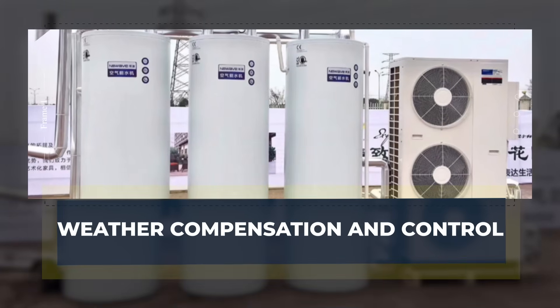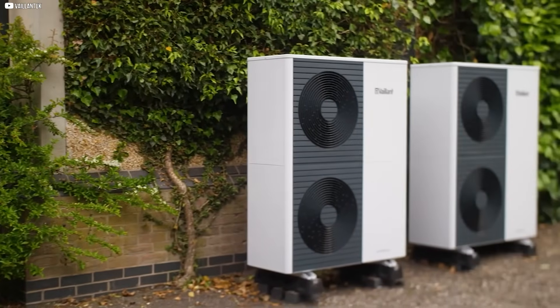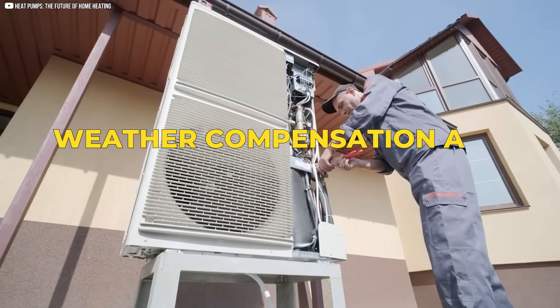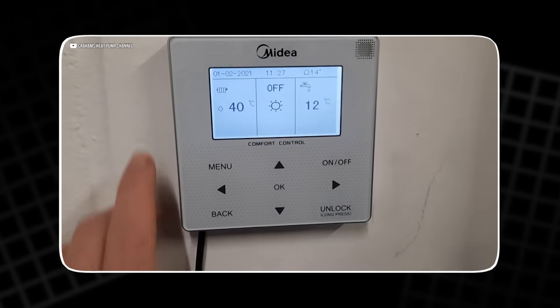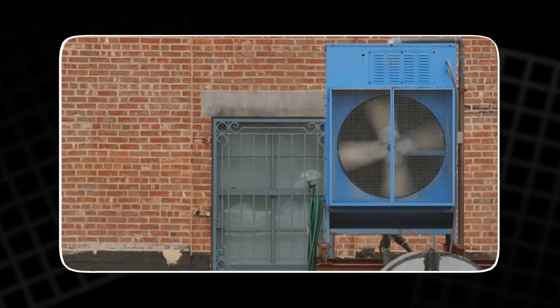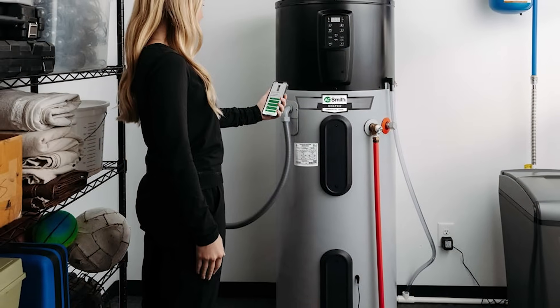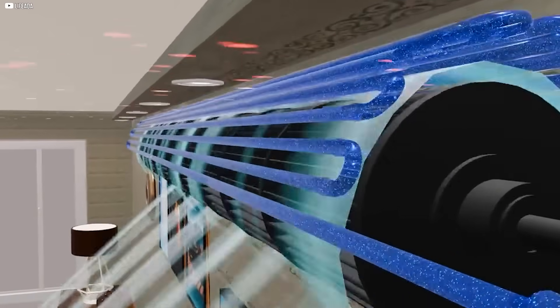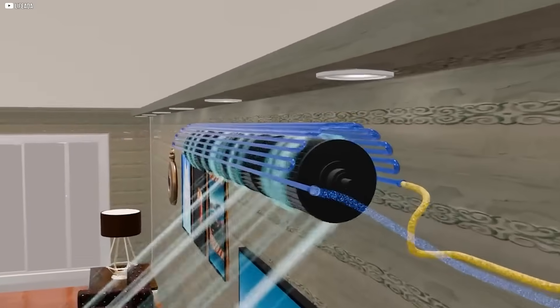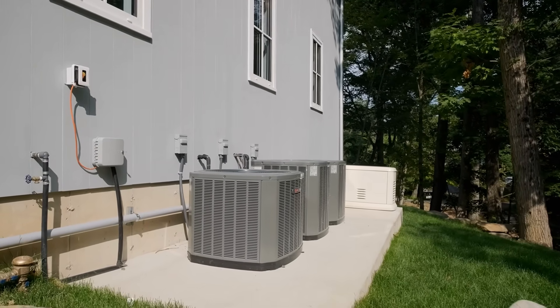Weather compensation and control. One of the most effective ways to optimize a heat pump's performance is through weather compensation and modulating controls. Traditional systems use on-off controls, meaning the system operates at full power until the desired temperature is reached, then shuts off. When the temperature drops slightly, the system turns back on to heat up again. This back-and-forth cycle not only wastes energy, but also causes the system to work harder than necessary.